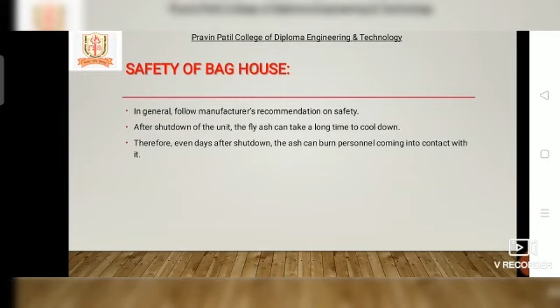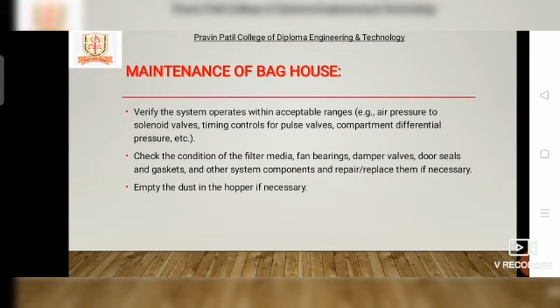Myself, Akanksha Baban Jadhav. Safety of the baghouse. In general, follow the manufacturer's recommendations on safety. After shutdown of the unit, the fly ash can take a long time to cool down. Therefore, even days after shutdown, the ash can burn personnel coming into contact with it. Maintenance of the baghouse: verify the system operates within acceptable ranges, for example air pressure to solenoid valves, timing control for pulse valve, compartment differential pressure, etc. Check the condition of the filter media, fan bearing, damper valves, door seals and gaskets and other system components and repair or replace them if necessary. Empty the dust in the hopper if necessary.